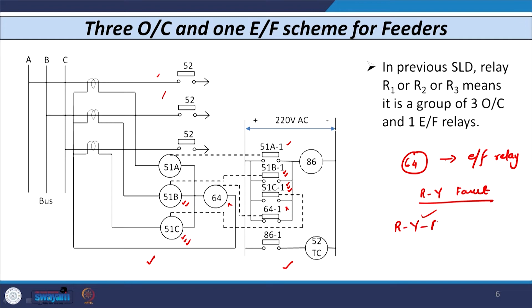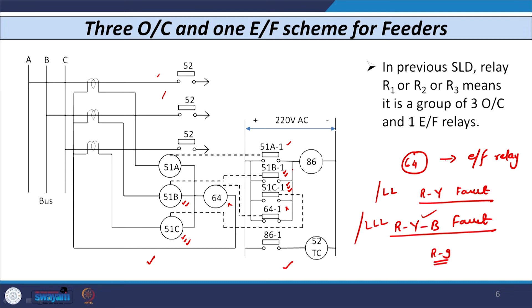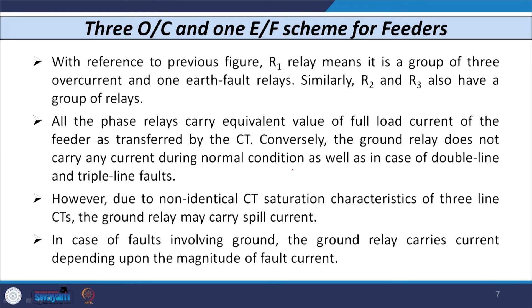In case of LL fault or triple L fault, no current flows through the ground unit 64 because it is a balanced condition. In case of a fault involving ground — say an R-to-ground fault — the current in the residual circuit increases, the contact 641 trips, which energizes relay 86, and further tripping is initiated. In each case, each relay operates for or is responsible for a different type of fault.